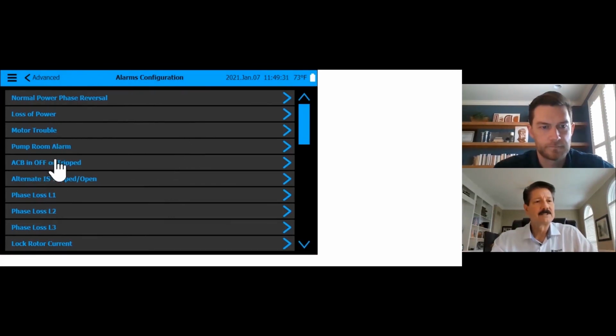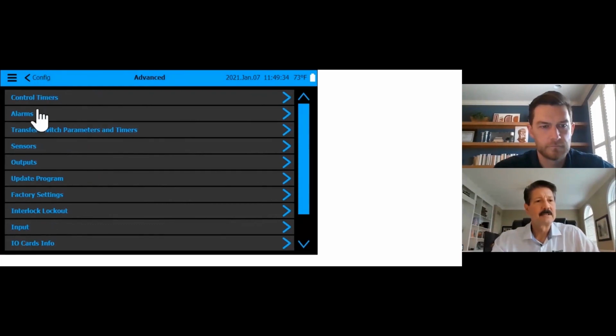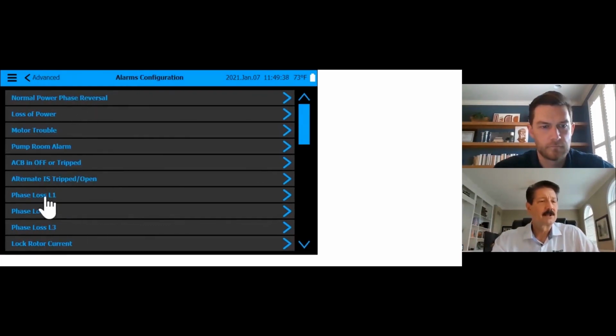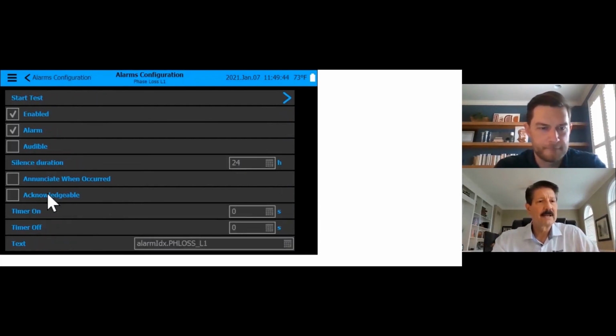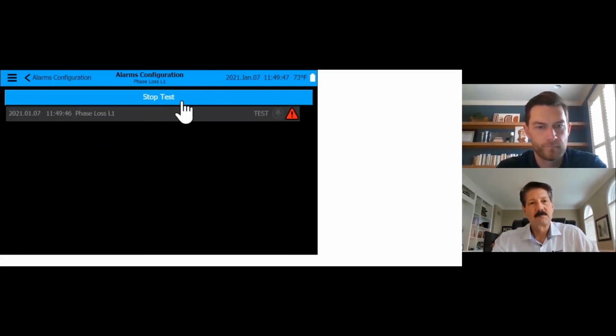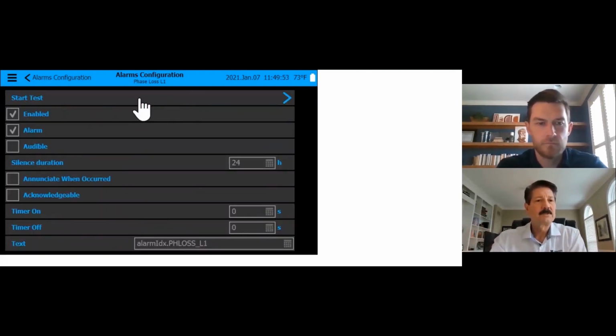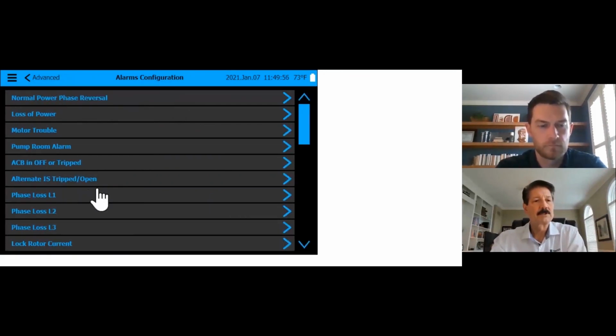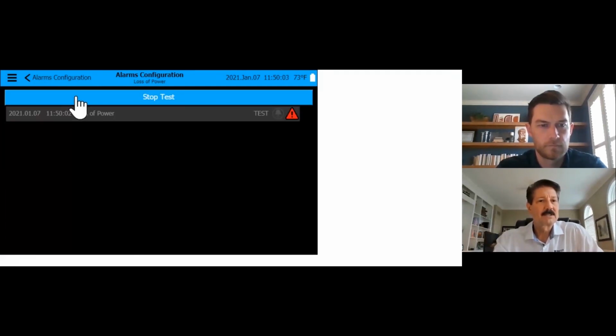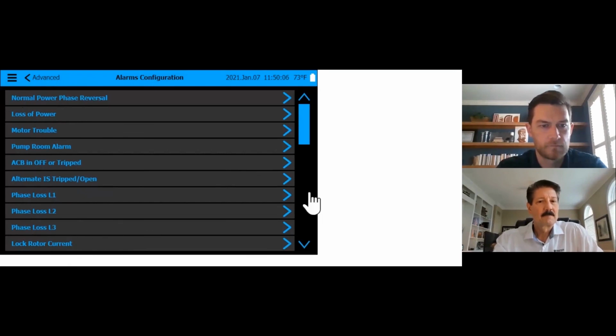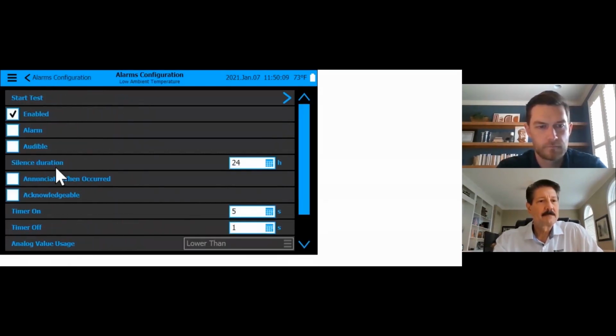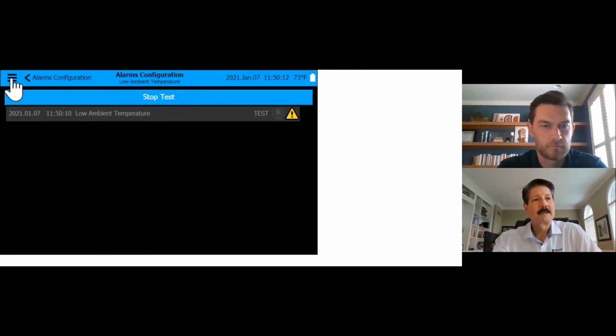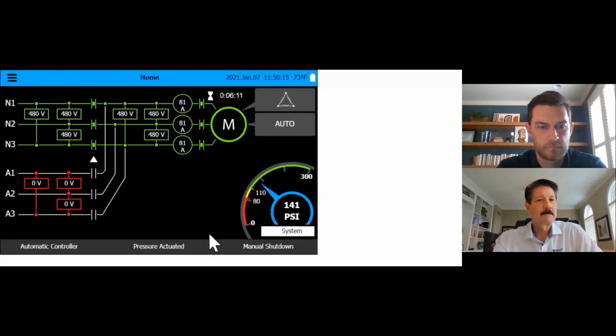Another thing we can do here is get into the alarms, like I mentioned, and pick any of these alarms. If we want to do a motor trouble, a pump room alarm, phase loss, we can actually do tests right here. If they're connected remotely to the annunciation panel, we can do tests right now on any of these alarms, as long as they're connected directly to that annunciation panel. Loss of power, obviously, start a test there. We can scroll down. Low ambient temperature, we can do a test there. And again, here's the home, low ambient temperature shown here.